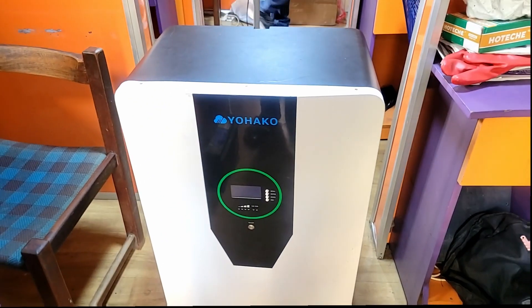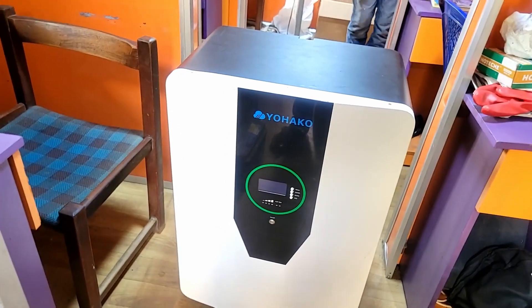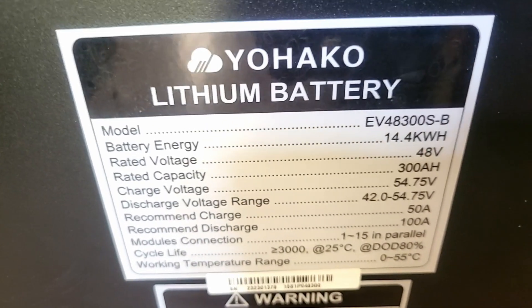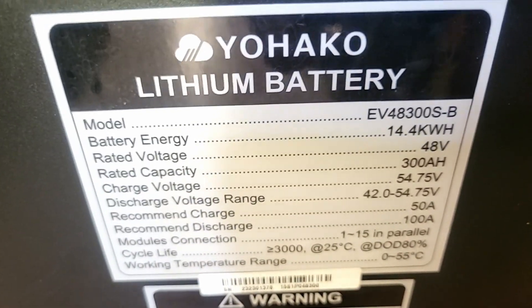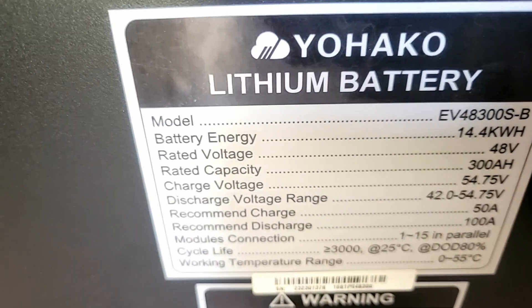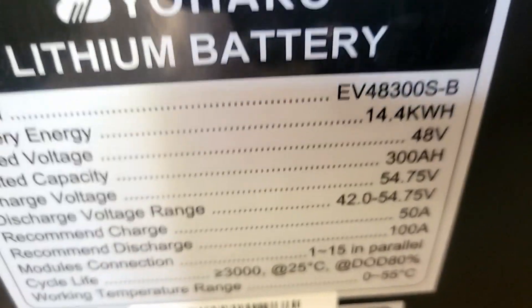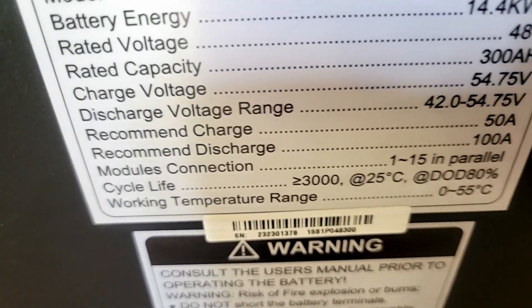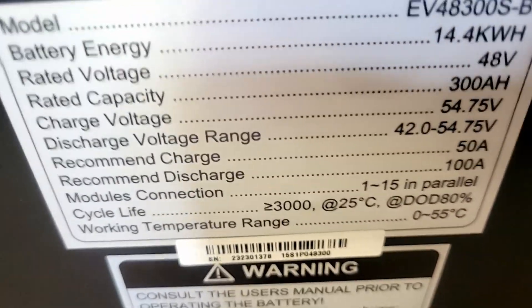The Yohako lithium battery label says: 14.4 kilowatt hours usable, 48 volts, 300 amp hours. The discharge voltage range is 42 to 54.75 volts. Now look at the recommended charge — that's 50 amps — and the recommended discharge: 100 amps.